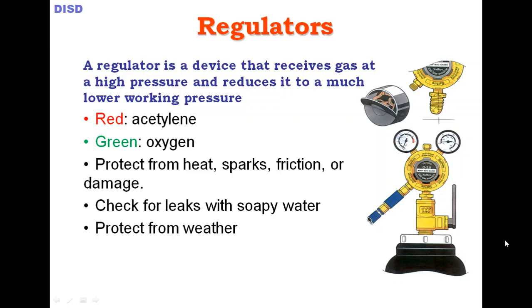Before using the regulator, ensure it is the correct type for the gas being used — do not interchange regulators between different gas types. After the regulator is attached, open it gradually. After use, close the valve before removing the regulator, and transport cylinders only after the regulator has been removed.